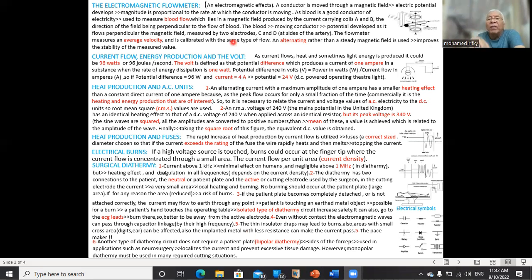The current goes through them, so it does not create problems as the monopolar does, and it's reliable in neurosurgery, so that I can be precise on the area where I'm going to use the current. But it is unfortunately not beneficial in large surgery, where we need monopolar current to induce a proper coagulation.